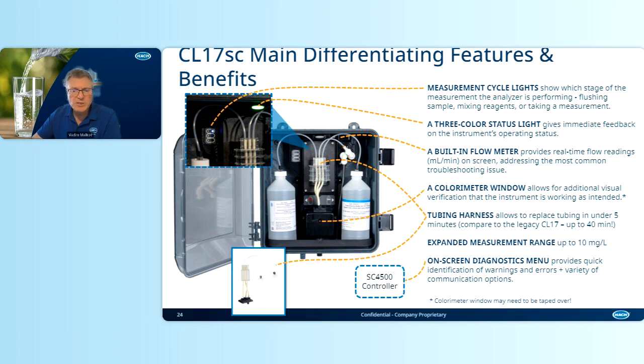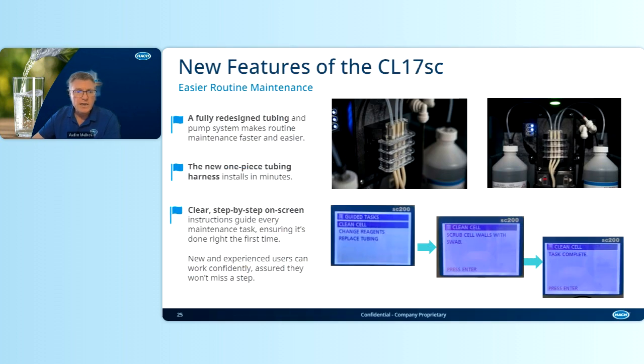The measurement range is expanded; compared to the legacy machine, it's double the range. And the on-screen diagnostic menus are presented on the SC controller. They provide quick identification of warnings and errors, and provide a variety of communication options. We're going to dive deeper into some of those features, particularly addressing routine maintenance. Those features provide much easier routine maintenance.